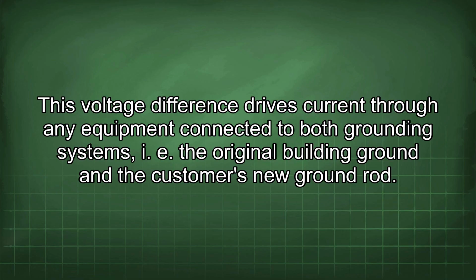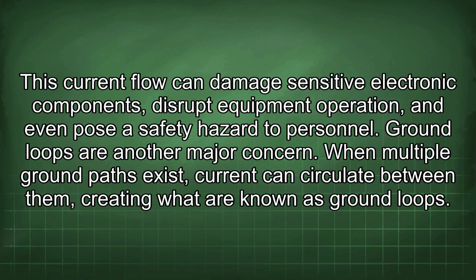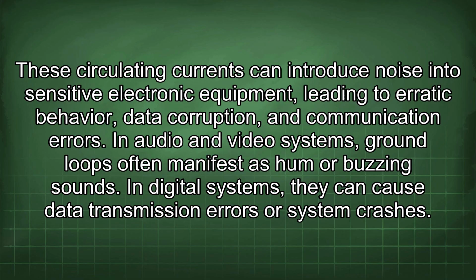This voltage difference drives current through any equipment connected to both grounding systems, i.e., the original building ground and the customer's new ground rod. This current flow can damage sensitive electronic components, disrupt equipment operation, and even pose a safety hazard to personnel. Ground loops are another major concern. When multiple ground paths exist, current can circulate between them, creating what are known as ground loops. These circulating currents can introduce noise into sensitive electronic equipment, leading to erratic behavior, data corruption, and communication errors. In audio and video systems, ground loops often manifest as hum or buzzing sounds. In digital systems, they can cause data transmission errors or system crashes.